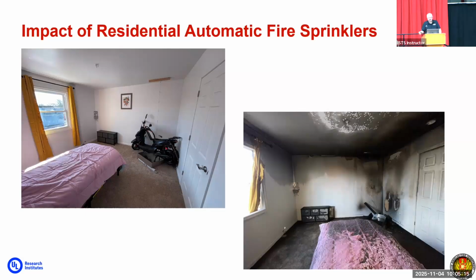The flash and the rapid fire development from the scooter caused enough radiant heat to start to pyrolyze and char the pink bedspread. But within seconds, the sprinkler was activated and that stopped any further fire development. So the batteries continued to off gas, they continued to burn, but the fire didn't spread. The sprinkler prevented flashover and limited the damage to the home.